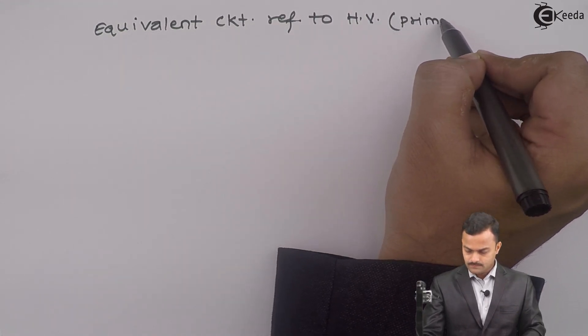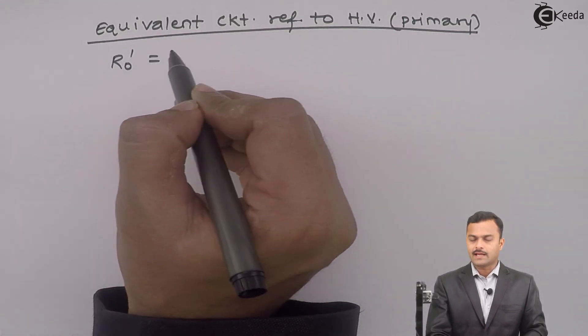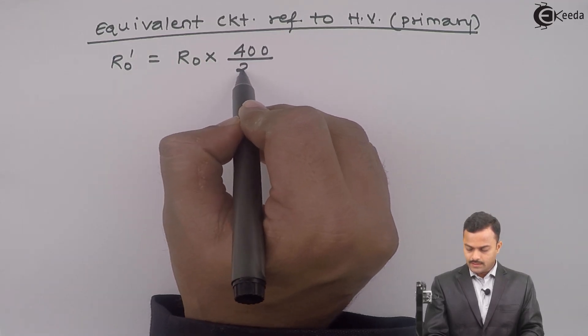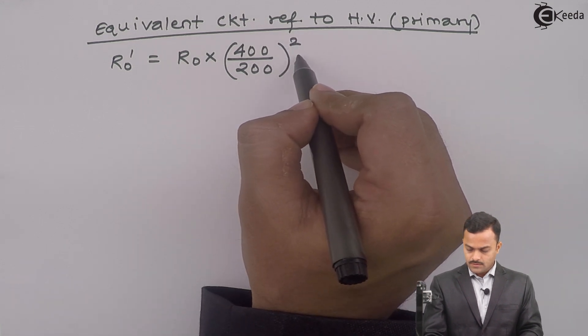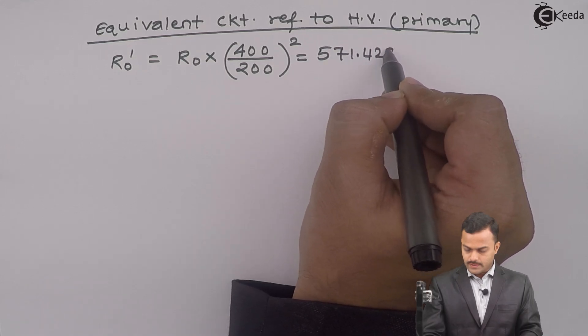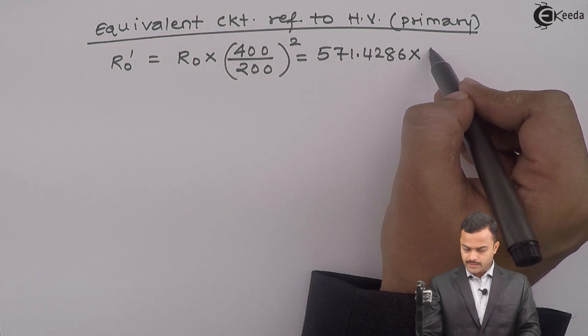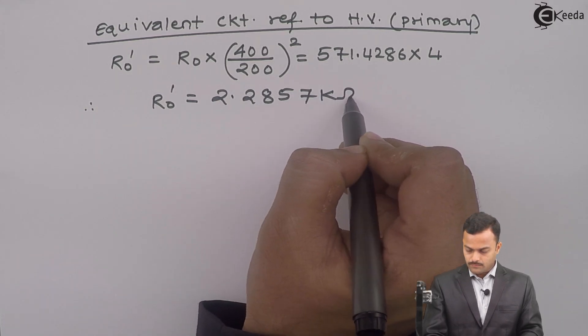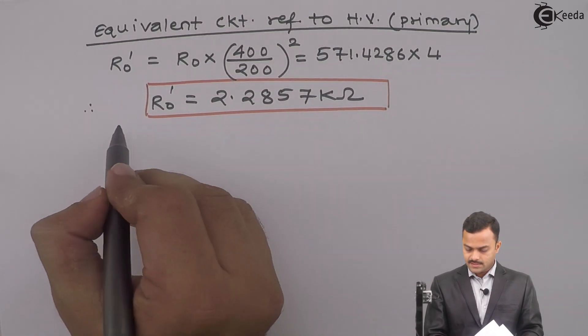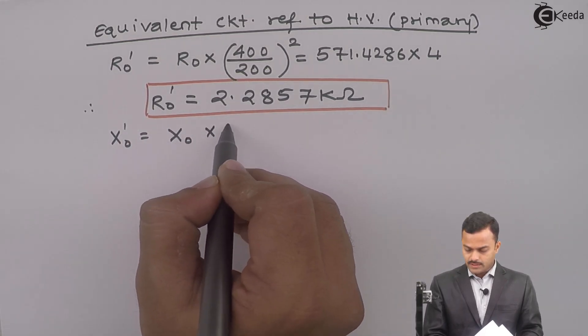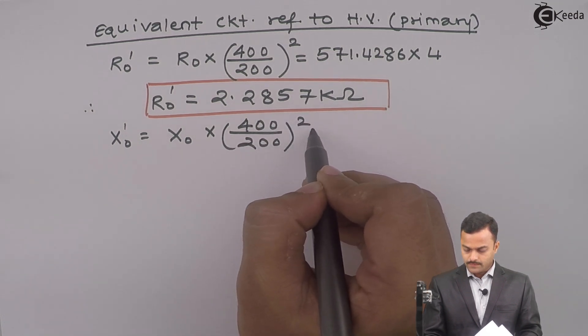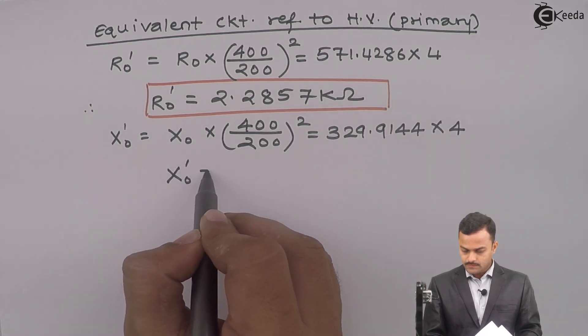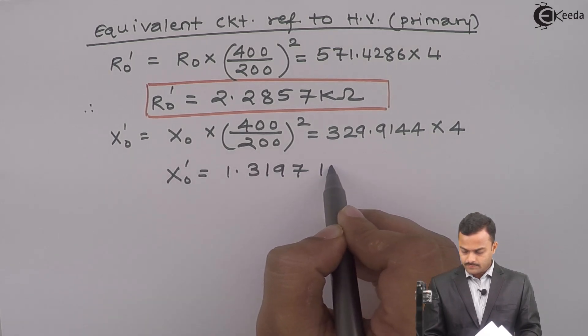Equivalent circuit referred to HV side will be like this. And HV side is our primary side. R0 dash we need to calculate. It is R0 multiplied by HV side voltage divided by LV side voltage square. This is equal to 571.4286 multiplied by 2 square is 4. So R0 dash you will get 2.2857 kilo ohm. Similarly, X0 dash equal to X0 multiplied by 400 upon 200 square which is equal to 329.9144 multiplied by 4. The answer will be 1.3197 kilo ohm.